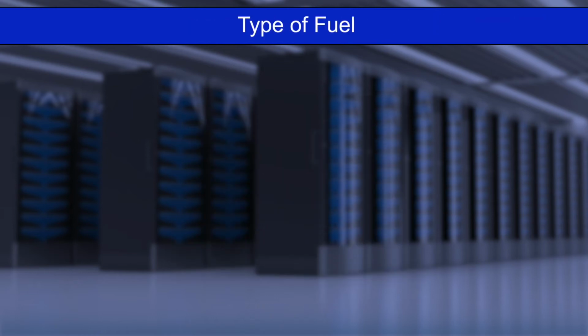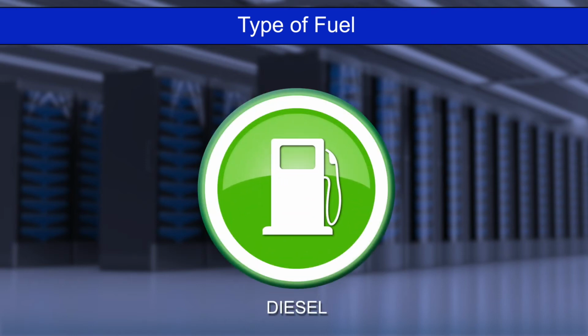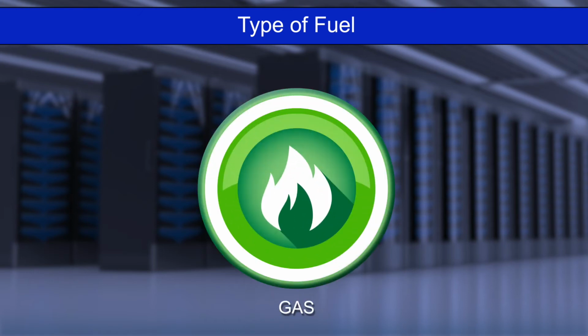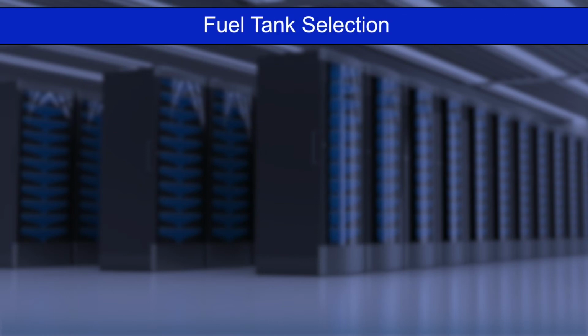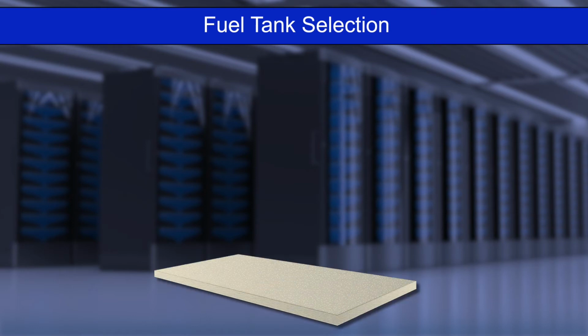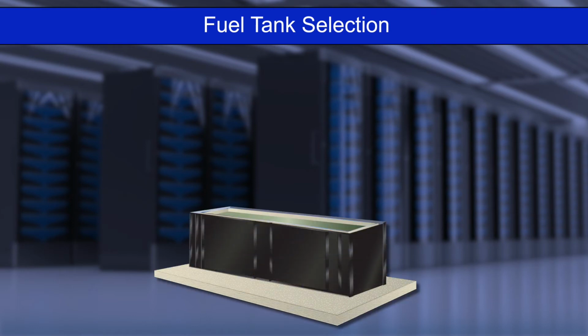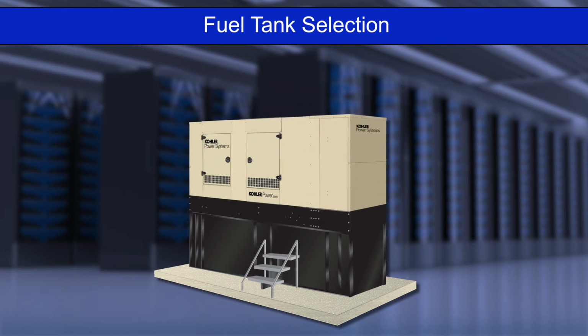The type of fuel required is a factor of availability and required performance. Many data centers prefer diesel engines with their ability to take full load quickly after initial run-up, but many systems utilize gaseous-powered generator sets. If a diesel generator is selected, on-site fuel storage must be specified. For an outside location, a concrete platform should be formed and poured. A UL-approved double-walled fuel tank for fuel spill containment will be mounted on the base. The generator set for an outside location can be mounted above the fuel tank.